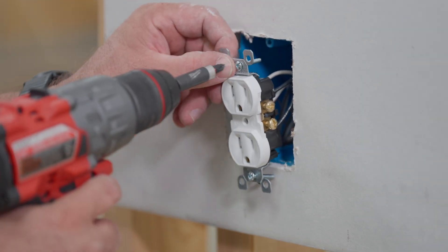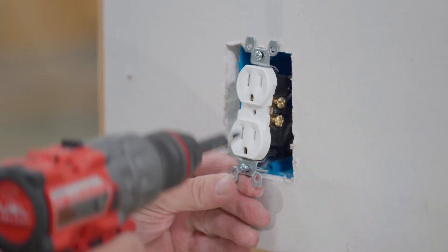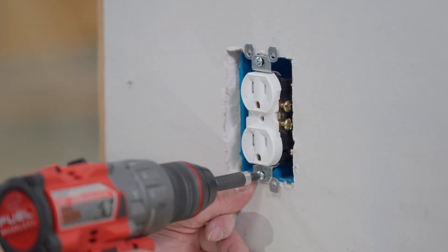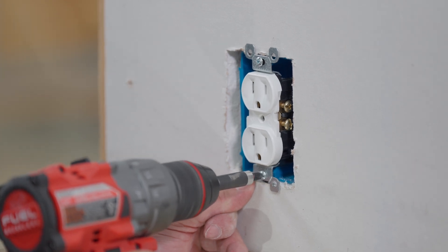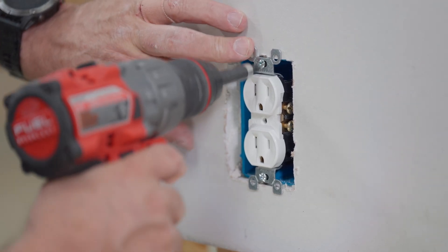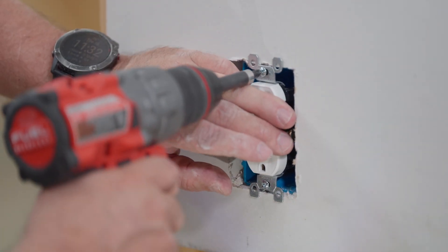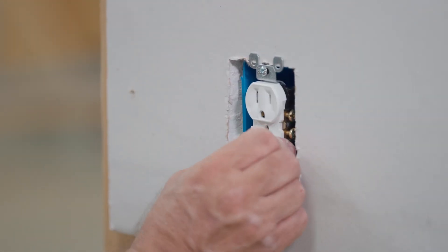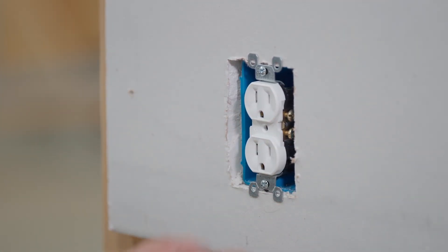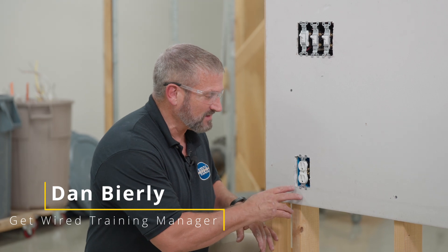And then you go right in here and carefully screw it in. You've got to be careful because this is a plastic box behind here, and a plastic box can get stripped very easily. You want to tighten it up. And what will happen is these boxes will flex forward a little bit, so you've got to be careful. It'll tighten and loosen up again because as you put pressure on it, it'll start to come forward. And eventually you'll hit equilibrium and it's good. Now you feel that. It's not going anywhere. It's tight. You can plug something in and it should be just about the right tightness for this particular installation. And this is a typical example of a residential receptacle outlet trim stage.